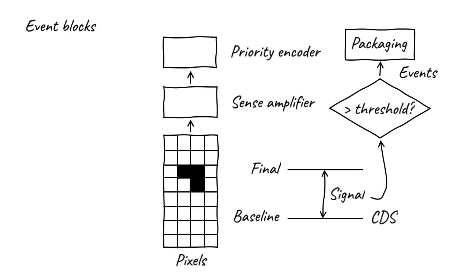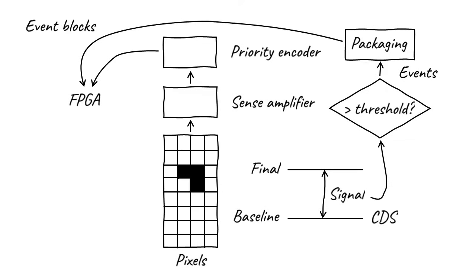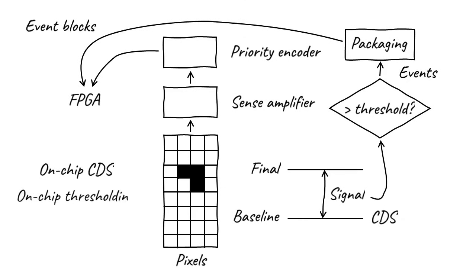Then finally, these event blocks are output from the sensor and sent to the onboard FPGAs for centroiding. Notice the things that are happening before anything is ever output from the sensor. Apollo has on-chip CDS to remove reset noise, on-chip thresholding to disregard background noise and identify real detection events, and digital noise-free output. This combination delivers both ultra-low noise and ultra-high speed.